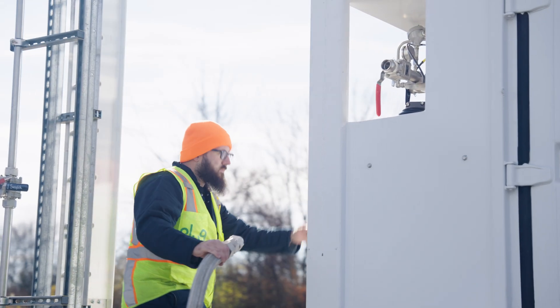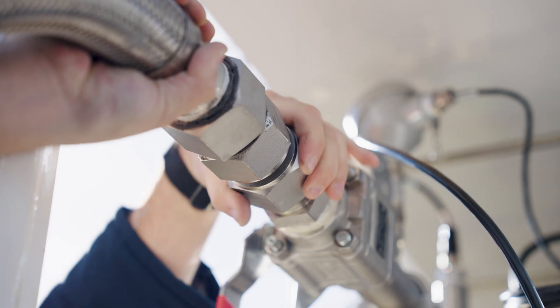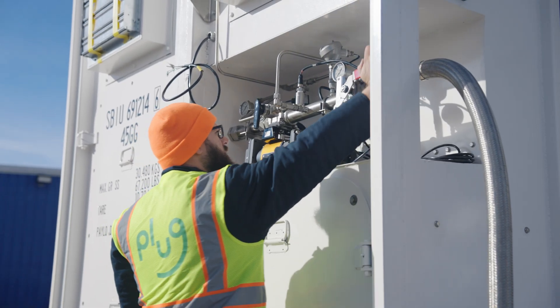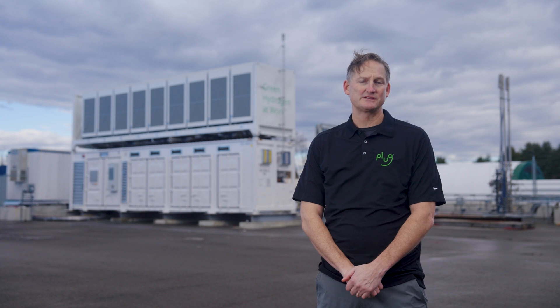The unit here is set up for verification testing. This is where the hydrogen connects. Our customers can choose to deploy gaseous hydrogen or liquid hydrogen tanks, the smallest being 15,000 gallons, scaling as large as customer needs. This two-thirds of the container holds five racks, each holding three ProGen 125s, and the architecture is designed for reliability, scalability, and redundancy. The chambers are designed to maintain a negative pressure on the fuel cells and are closely monitored to ensure safety.